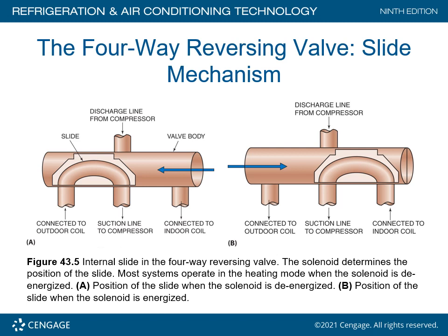Now, this is a four-way reversing valve slide mechanism. So basically, you notice right here, in this position, the slide is internal, basically connecting up to the outdoor coil, suction line of the compressor. And then this line is connected to the indoor coil. Okay, so in figure A, position of the slide when the solenoid is de-energized.